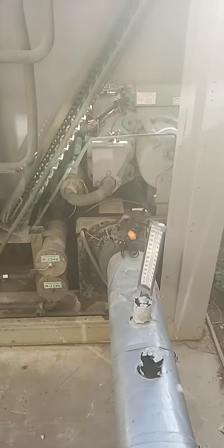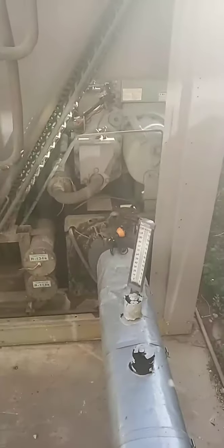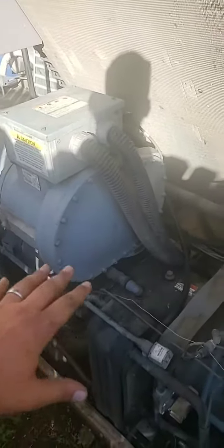After the oil pump circulates and runs, then it engages our compressor fully unloaded. Which reminds me, I didn't talk about the unloader. Like I said, if I'm losing anybody, shout out, please. Once the compressor comes on fully unloaded, meaning that it's running at minimum capacity, and yes, these compressors can run at different capacities, and it stabilizes, and the system recognizes that, okay, I'm running at a stable load, stable pressures, then it starts to stage up the compressor so it'll handle more capacity. That way, as it needs to, depending on how quickly the water temp is dropping and how well the compressor itself is doing. If it sees that the compressor is going to push itself into a fault condition by staging up, it's going to hold it back.